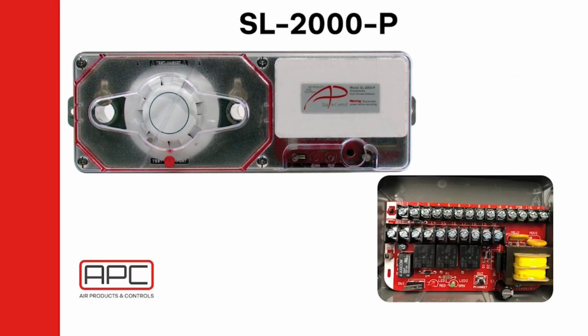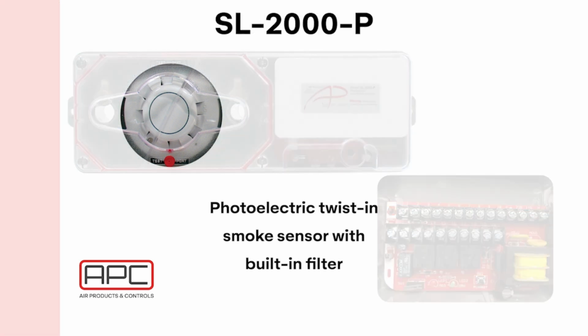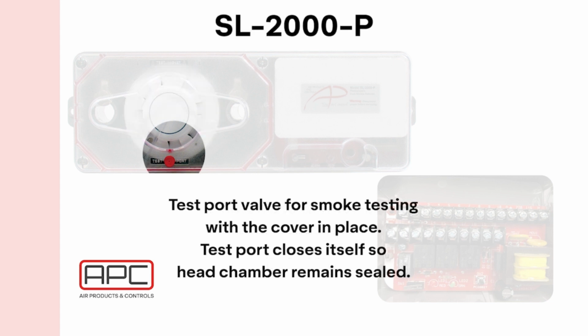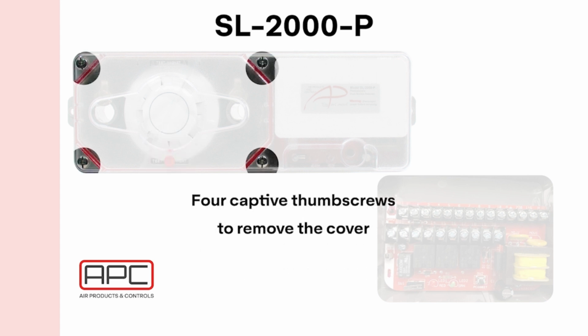The SL2000 is a conventional 4-wire duct smoke detector, offered with a twist-in photoelectric sensor, which is field replaceable and has a built-in filter. There is a test port valve that is for quick testing with aerosol smoke. This self-closes so the chamber remains sealed after testing is complete. 4 captive thumb screws remove the cover quickly and with no tools required.